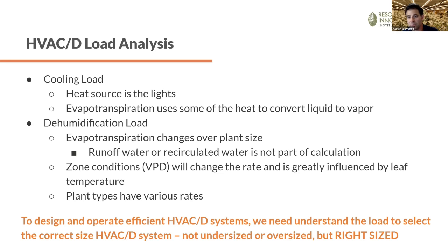And that's what VPD is. If you look at a VPD curve, a VPD graph, you have temperature and relative humidity as your two axes. So understanding the conditions that we want to maintain in that space, based upon the plant growth and the time at which that plant is in the cycle, is going to help dictate what environmental conditions we want to maintain. And that changes throughout the cycle, right? Not only does the load profile change every single day from lights on to lights off, it's changing as the plants grow from clones into teens, into early stage flower, late stage flower, and then into harvest.